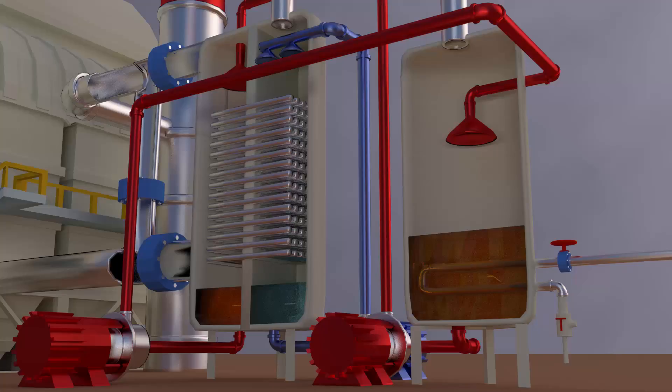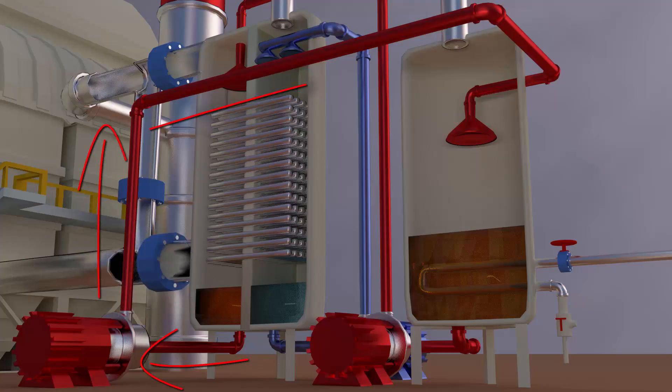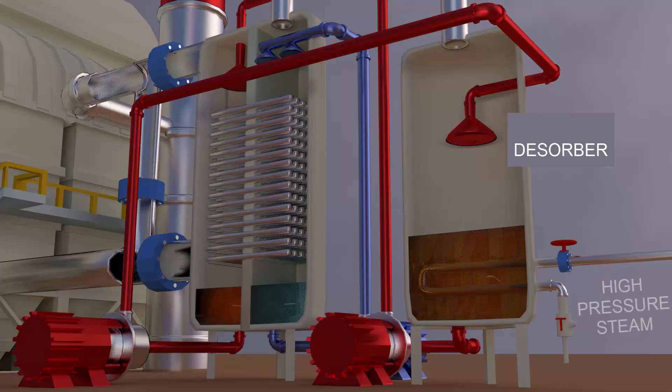As it passes through the absorption chamber, the brine becomes more dilute. In order to be reused, it must be regenerated to its original concentration. It is pumped to a still, where all the absorbed water is boiled out at atmospheric pressure. High-pressure plant steam is used to drive this boiling.